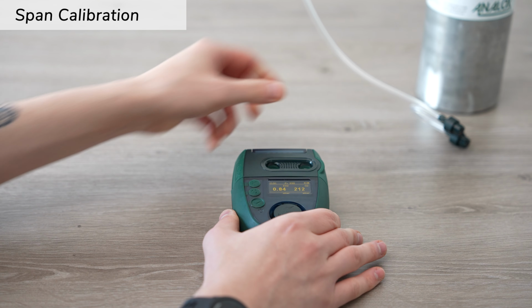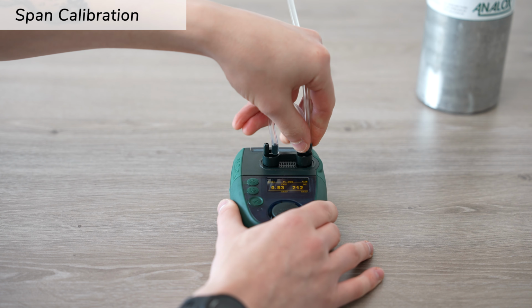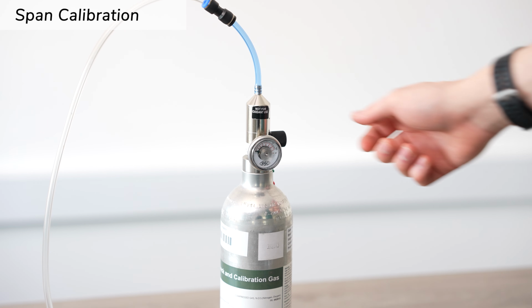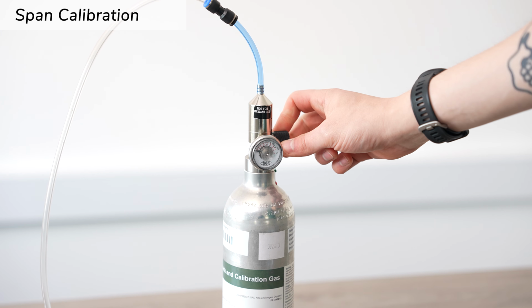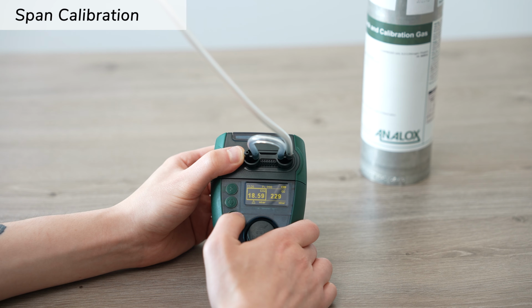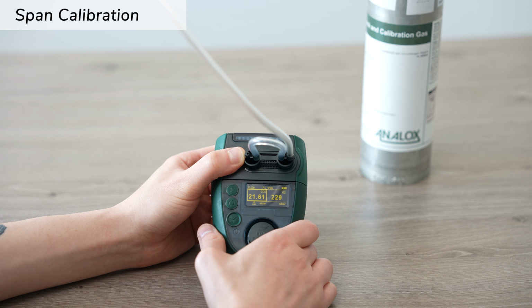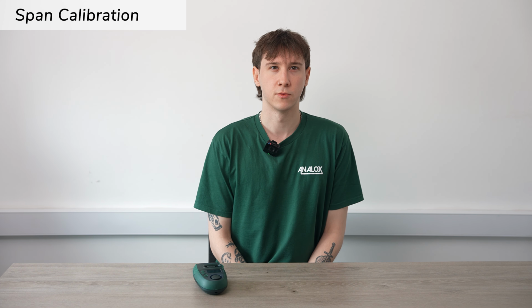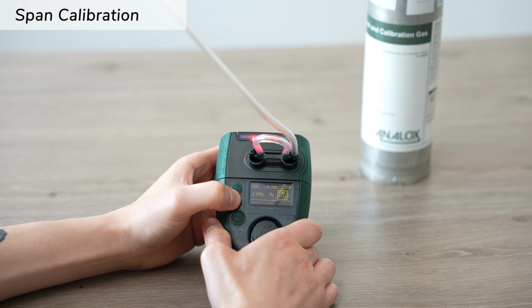While this is happening, we can set up our span calibration gas. Although we recommend 3%, you can use up to 5% CO₂ to calibrate. We start again by connecting the span calibration gas to the sensor and opening the regulator valve to ½ litre per minute. This will cause the unit to go into alarm, but these alarms can be muted using the OK button. Once the reading is stabilised, we can enter the menu again, accessing high calibration for CO₂.